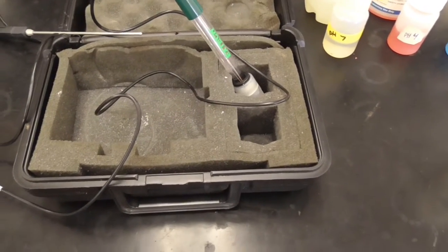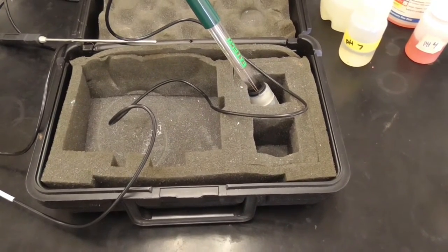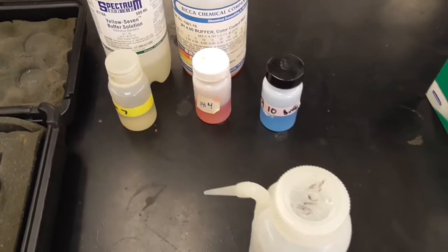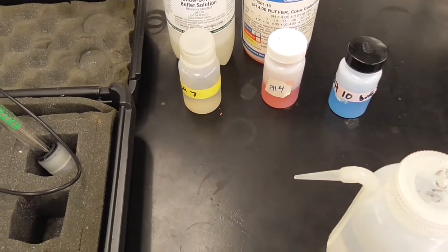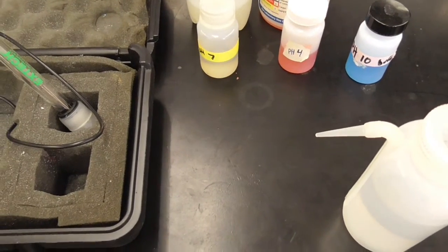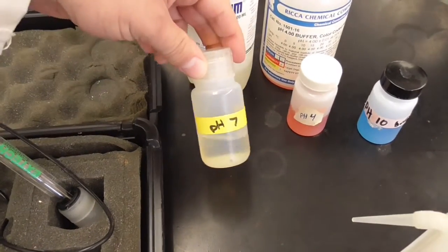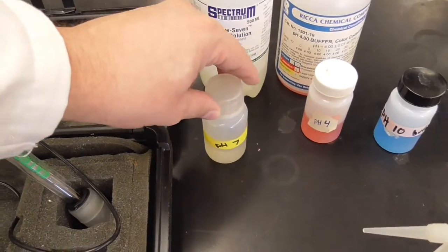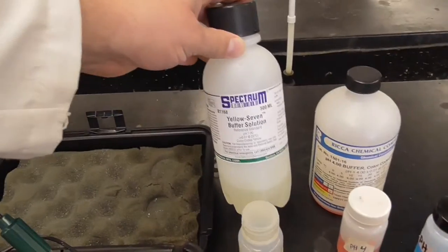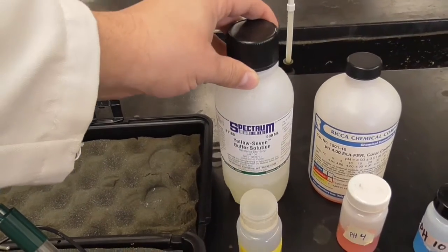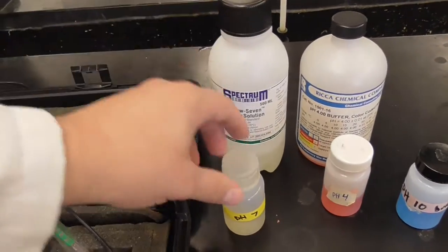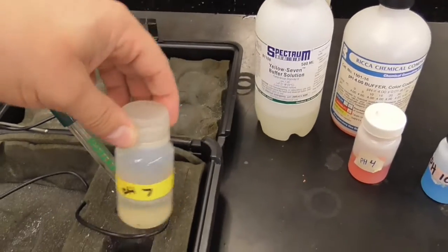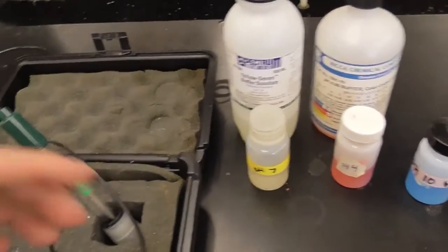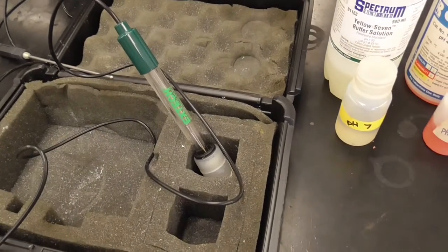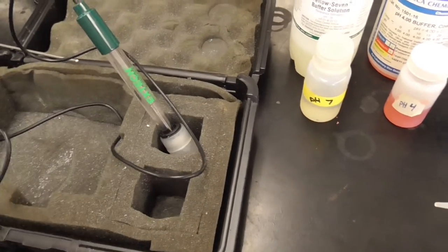All right, so we've got the pH probe, and I'm going to show you how to calibrate this. In order to do that, you need buffers. Okay, buffers at different pH values, standards basically. Every time you always need a pH 7 standard. It's color coded. 7 is the yellow 7 buffer solution, or faint yellow anyway. And a lot of times, there's a couple of these bottles in the case here with the pH meter, because the probe is stored separately.